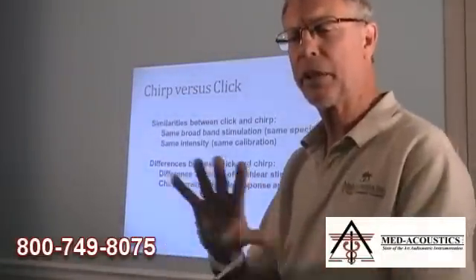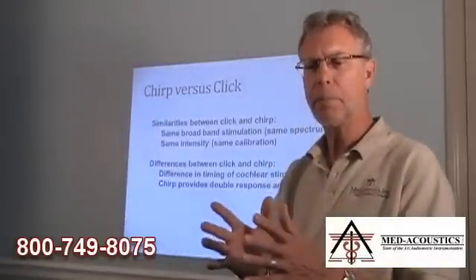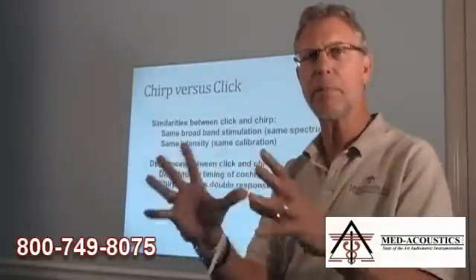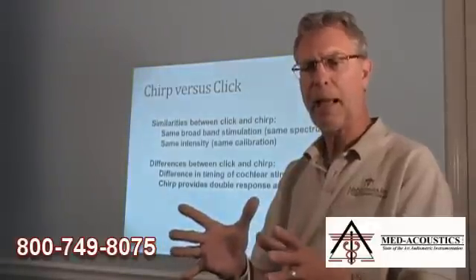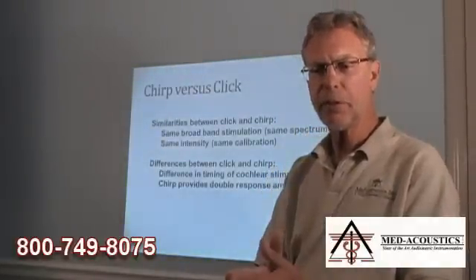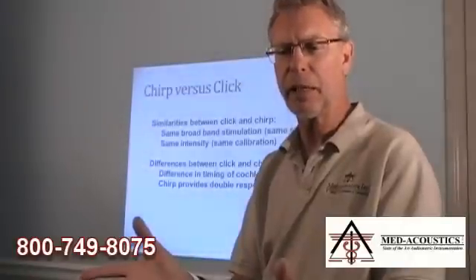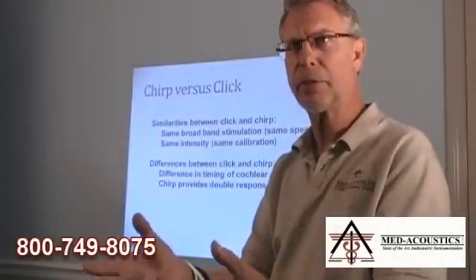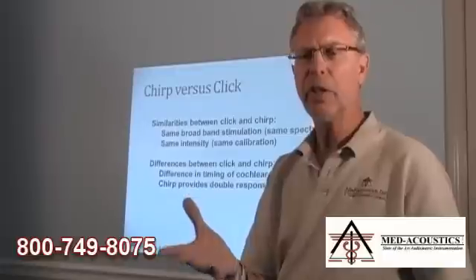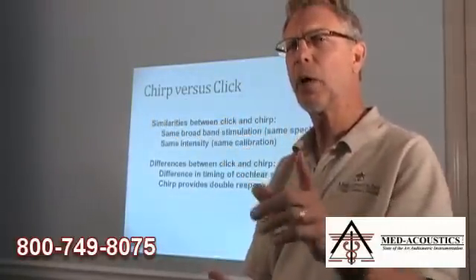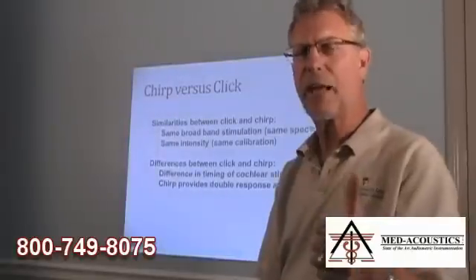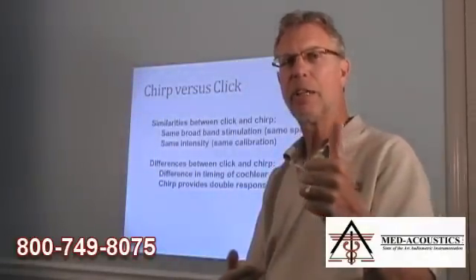What's the difference between the chirp and the click? The similarities are that they are both broadband stimulations with the same spectrum of frequencies, the same intensity, and the same calibration. The difference is in the timing of the cochlear stimulation — it's a more efficient timed stimulation, and it produces double the response. When we can produce a higher amplitude response, we can get it faster because we have to do much less averaging.